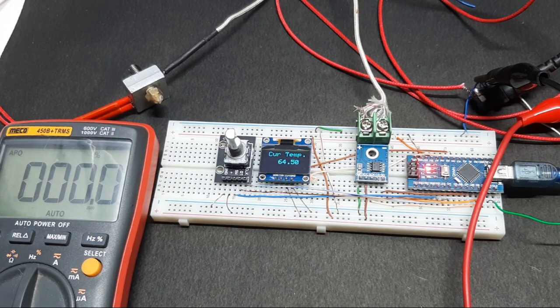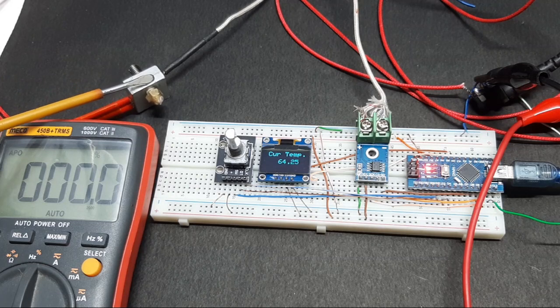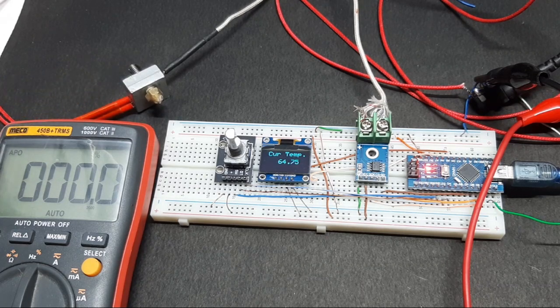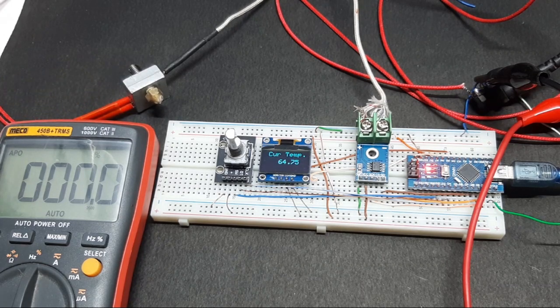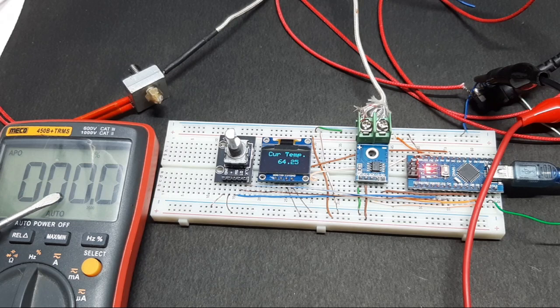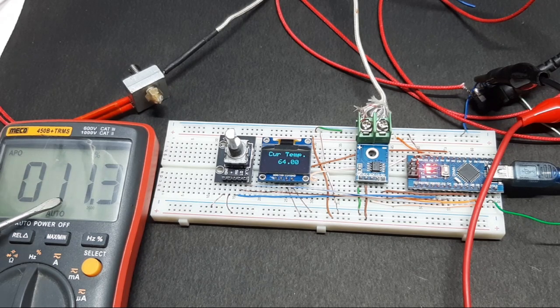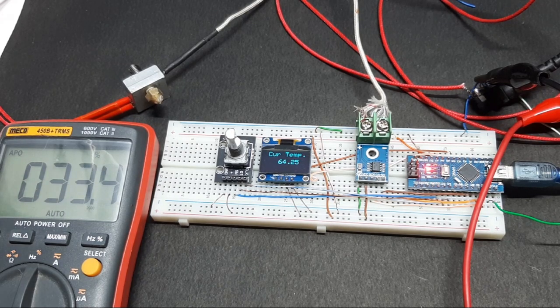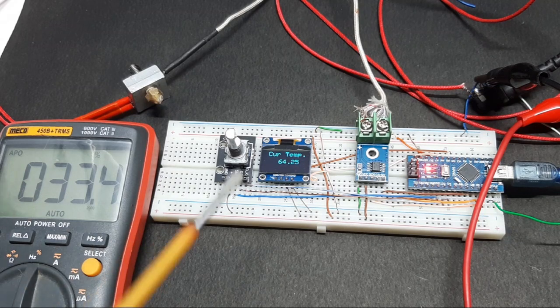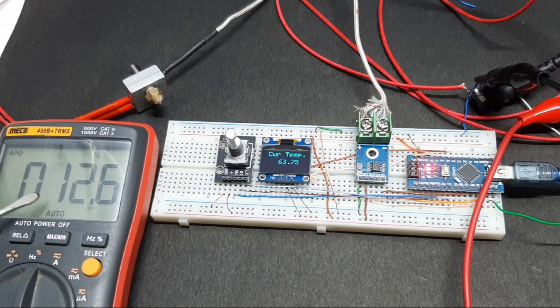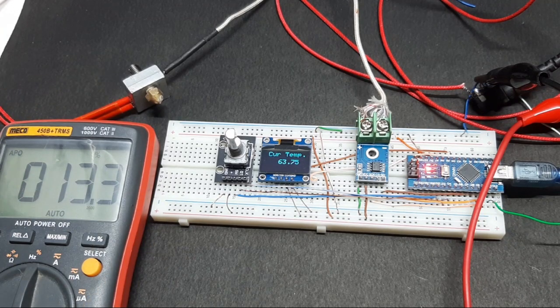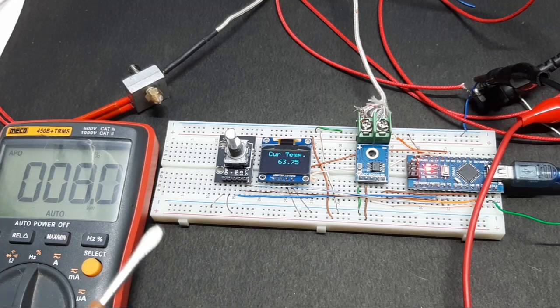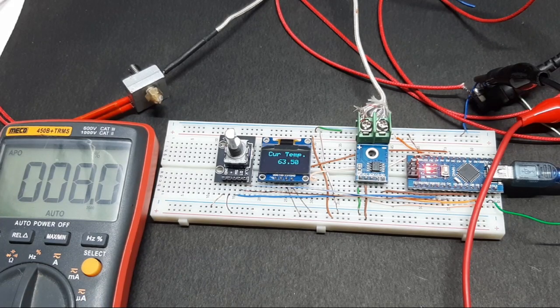When the heater block cools down a little, as you can see, there's a sudden spike in the duty cycle. There's an 11 percent spike, then a 33 percent spike. The temperature goes up, the duty cycle goes down, and it maintains the temperature that way.